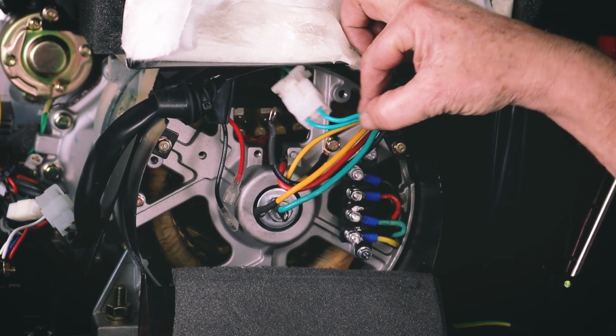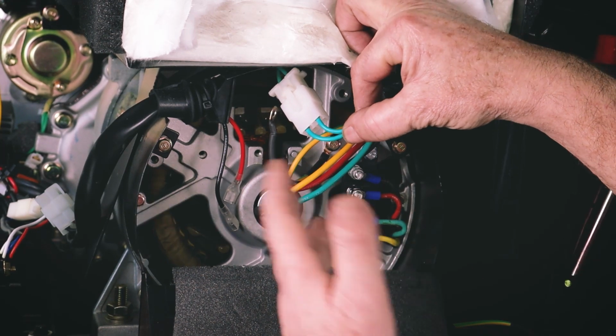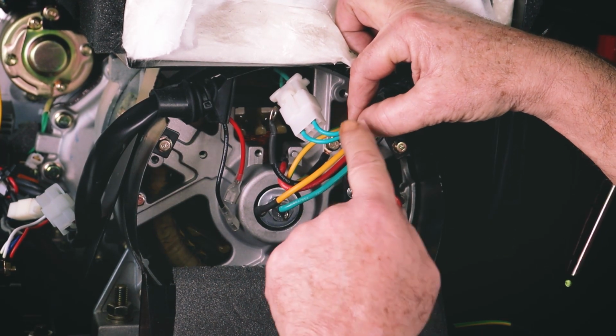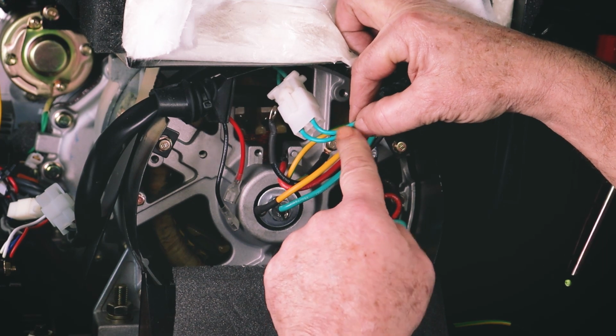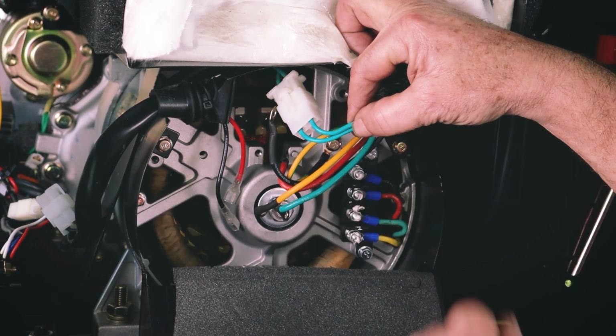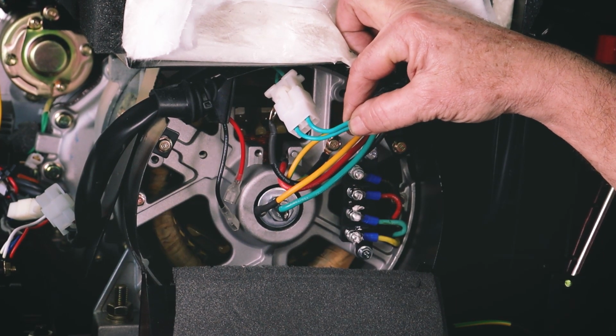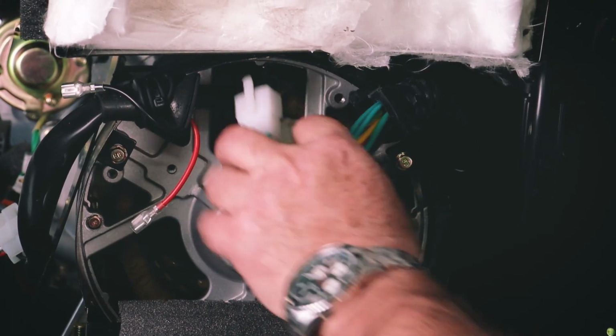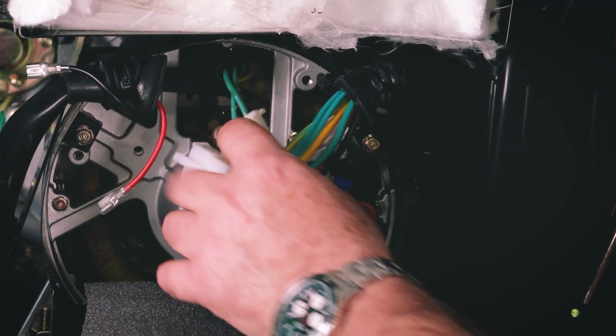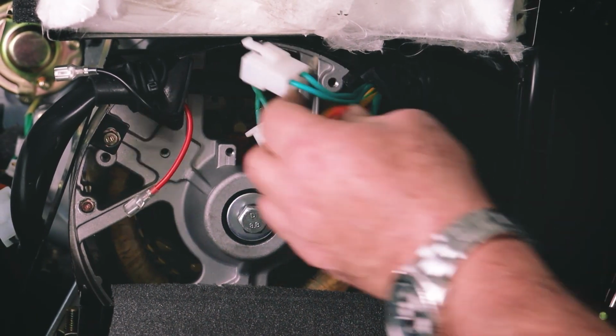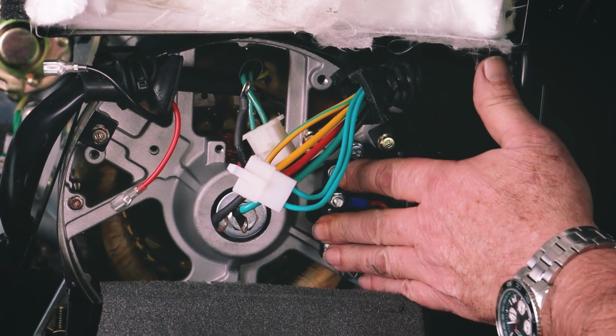So this is what supplies the power, or it is an AC, it goes through a rectifier, but it's a low voltage AC output. And this basically goes to the control panel to supply the 12-volt output socket on the control panel. That plug's disconnected. Everything's disconnected other than the ground wire, which is absolutely fine. I can leave that there. So these terminals are all disconnected.